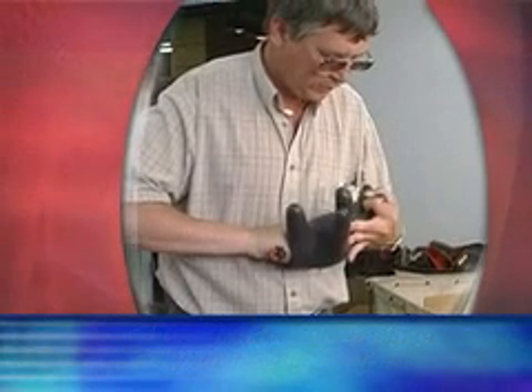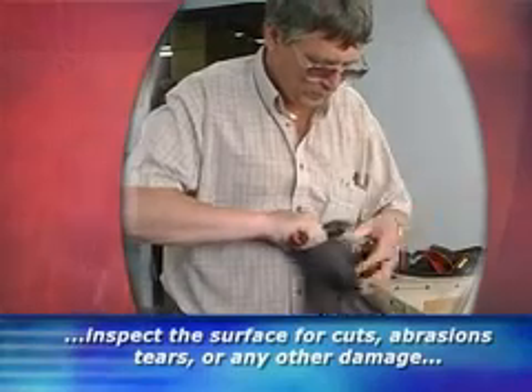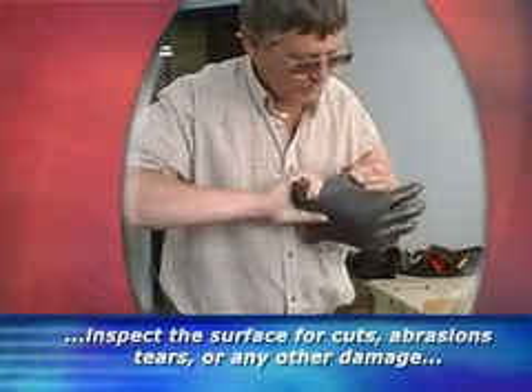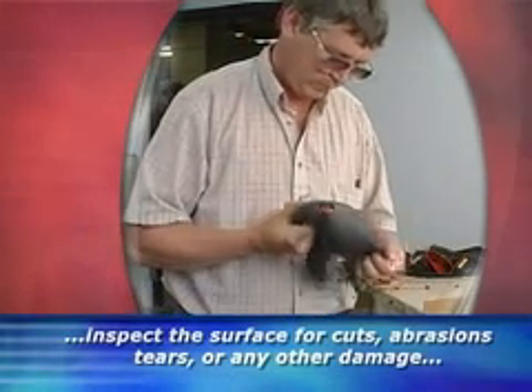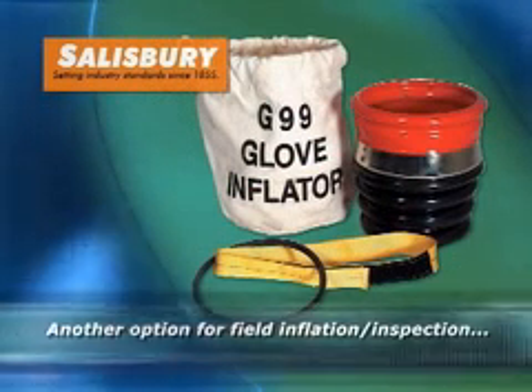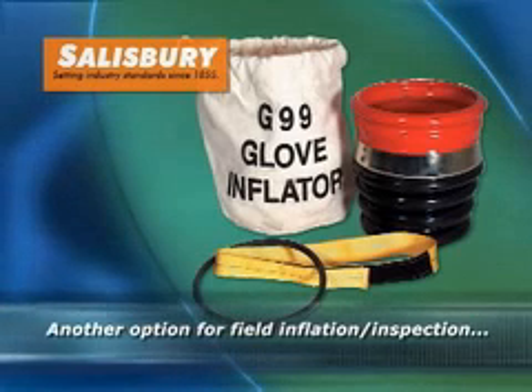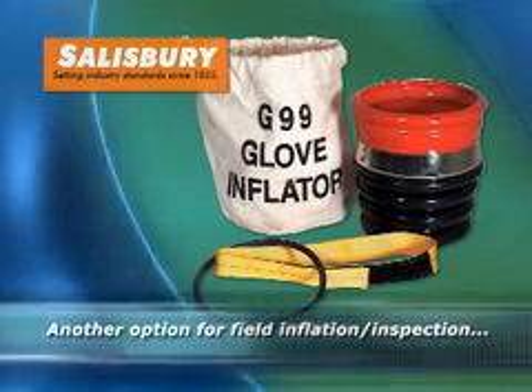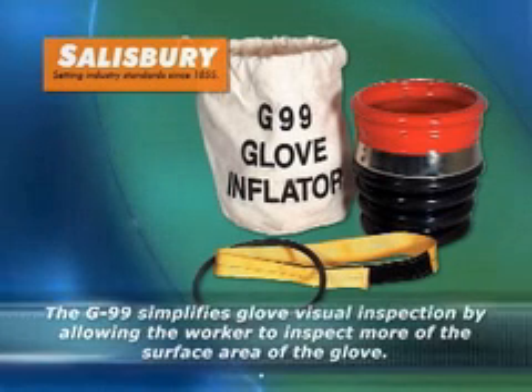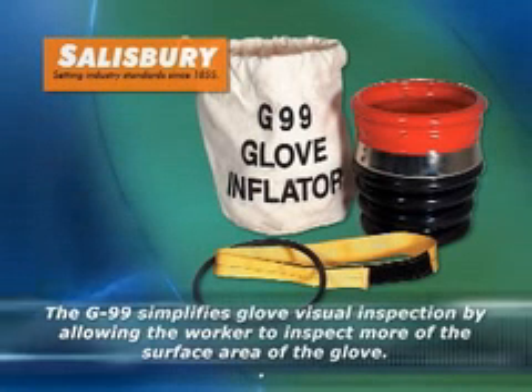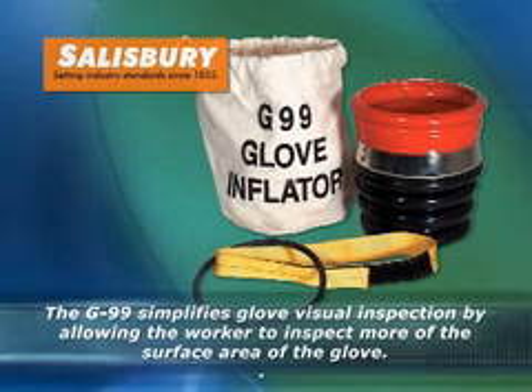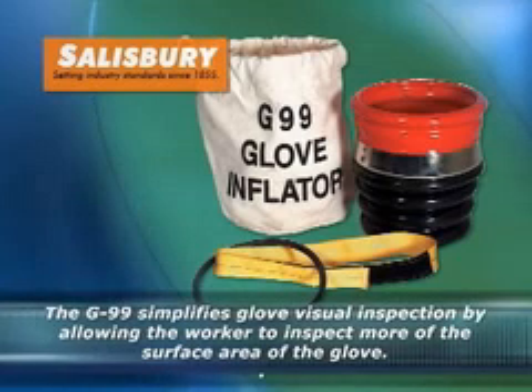While the glove is inflated, inspect the surface for cuts, abrasions, tears, or any other damage that may affect the integrity of the insulating glove. Another option for field inflation and inspection is to use Salisbury's portable G99 glove inflator. The G99 simplifies visual inspection and inflation by allowing the worker to inspect more of the surface area of the glove.